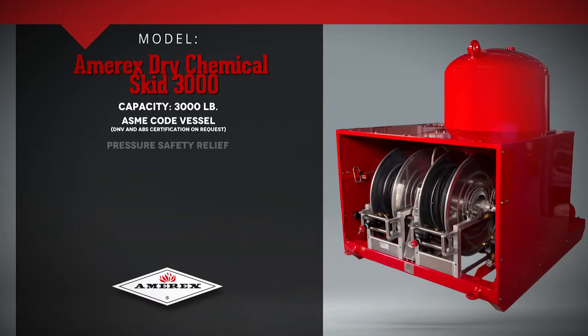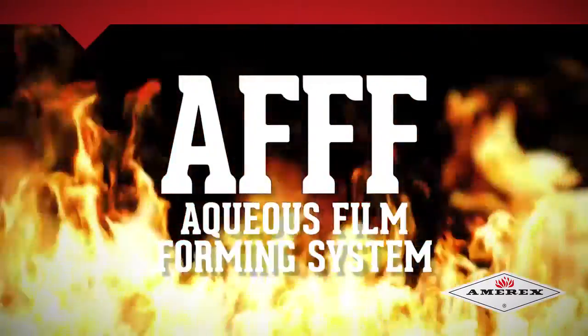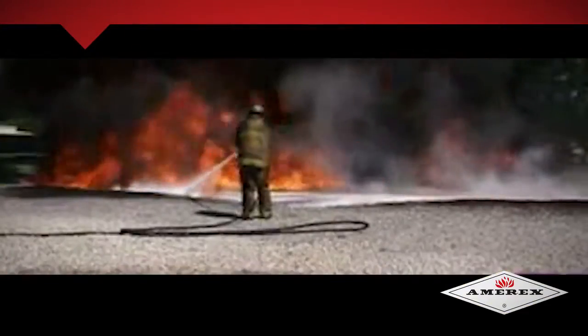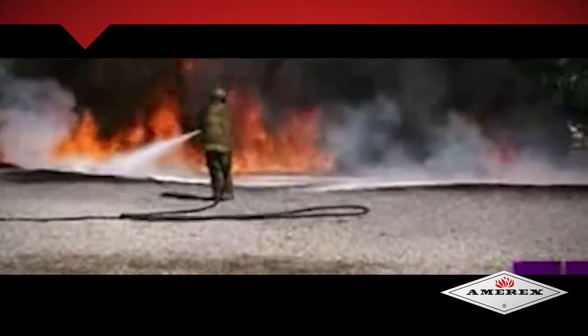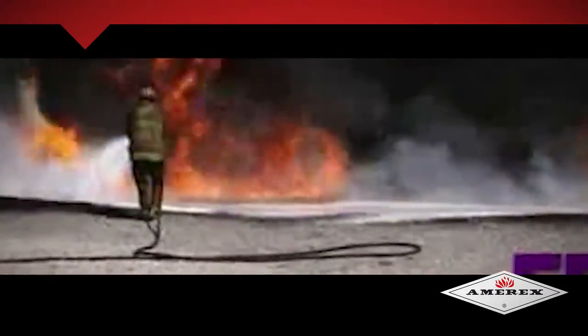The Amerex Dry Chem Skid 3000. Amerex Aqueous Film Forming Foam Systems, AFFF, are the latest in AFFF fire suppression. Amerex AFFFs are self-contained Class A or B fire protection systems that deliver a premixed foam solution, blanketing and smothering a fuel source while acting as a vapor suppression to aid and prevent re-ignition. Amerex AFFF units are totally self-contained and require no outside water, foam pumps, or proportioners.